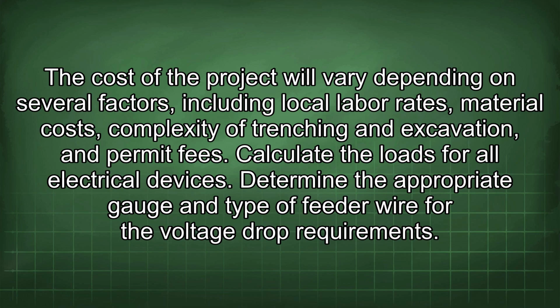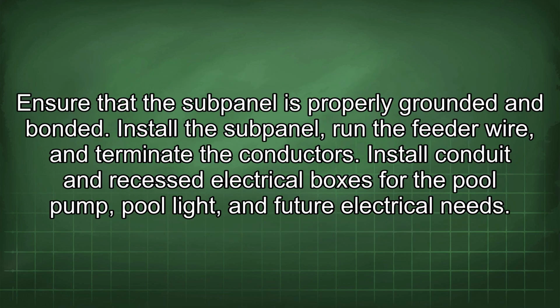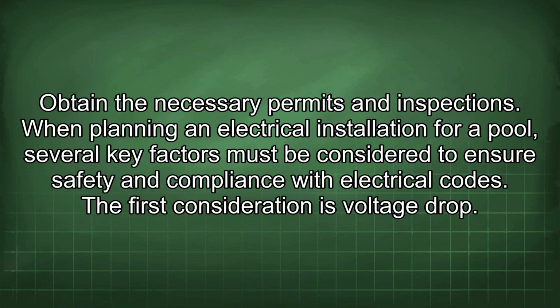The cost of the project will vary depending on several factors, including local labor rates, material costs, complexity of trenching and excavation, and permit fees. Calculate the loads for all electrical devices. Determine the appropriate gauge and type of feeder wire for the voltage drop requirements. Ensure that the subpanel is properly grounded and bonded. Install the subpanel, run the feeder wire, and terminate the conductors. Install conduit and recessed electrical boxes for the pool pump, pool light, and future electrical needs. Obtain the necessary permits and inspections.